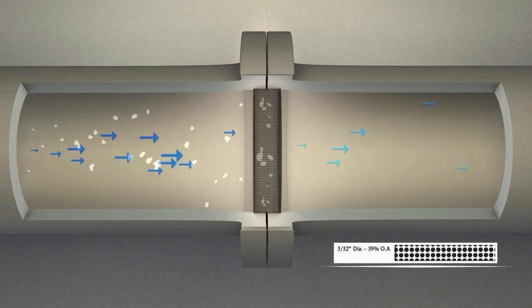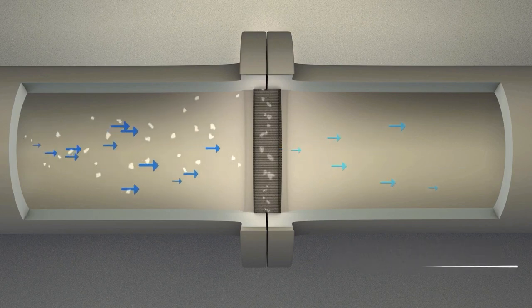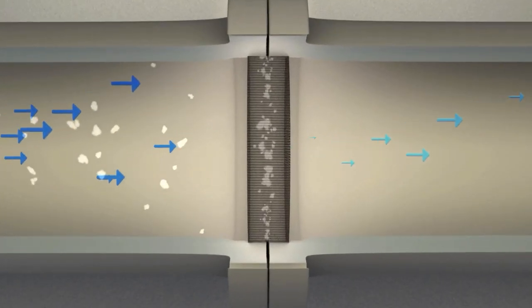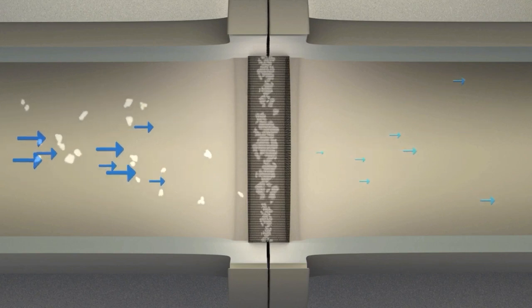Filters and strainers commonly are positioned to capture solids and particulates. The filter will obstruct the flow through the pipe, lowering the pressure on the downstream side. These effects may vary depending on the filter's construction. Filter media is the material that removes impurities. The smaller the pores, the larger the friction. Higher friction means greater pressure drop.